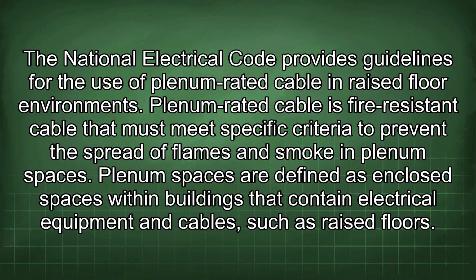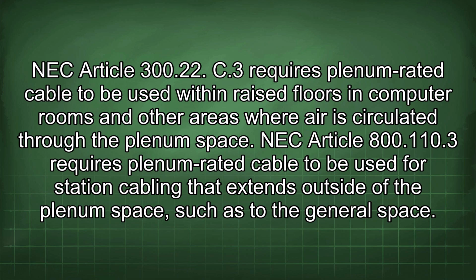The National Electrical Code provides guidelines for the use of plenum-rated cable in raised floor environments. Plenum-rated cable is fire-resistant cable that must meet specific criteria to prevent the spread of flames and smoke in plenum spaces. Plenum spaces are defined as enclosed spaces within buildings that contain electrical equipment and cables such as raised floors. NEC Article 300.22 C3 requires plenum-rated cable to be used within raised floors in computer rooms and other areas where air is circulated through the plenum space.